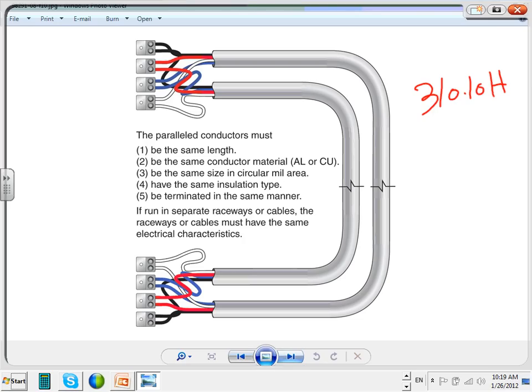When you parallel conductors, they have to be the same length. The conductors have to be the same material, copper or aluminum, the same size, the same insulation, and terminated in the same manner, with the same type of lugs. And the raceway or the cable must be the same type of raceway and the same type of cable.